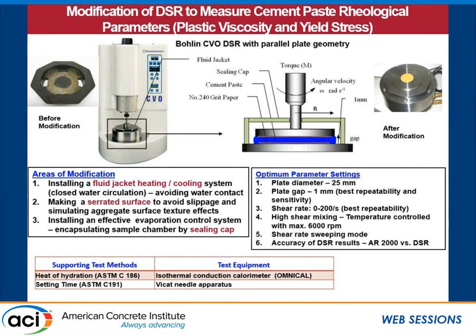We made these modifications: a sealing cap to minimize evaporation, a 240-grit paper introduced to give some texture to the plates to prevent slippage, and we totally changed the heating system to what is called a fluid jacket after modification, so water doesn't come in contact with the cement paste. We also did some preliminary investigation to determine the gap between the two plates, and found that a one millimeter gap is optimum for better repeatability. We selected a shear rate of 0 to 200 per second for best repeatability. We developed a high shear mixing procedure based on NIST and Portland Cement Association guidelines, used a shear rate sweeping mode, and used another rheometer to verify the DSR results. We also used a calorimeter and setting time as supporting tools.